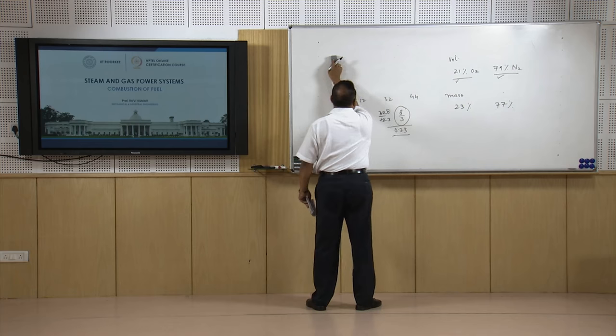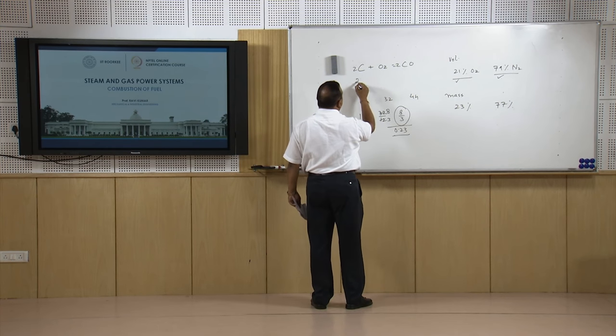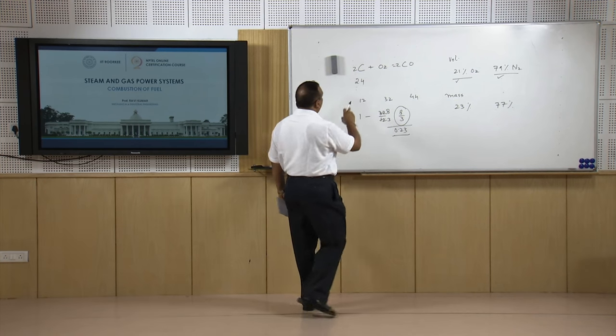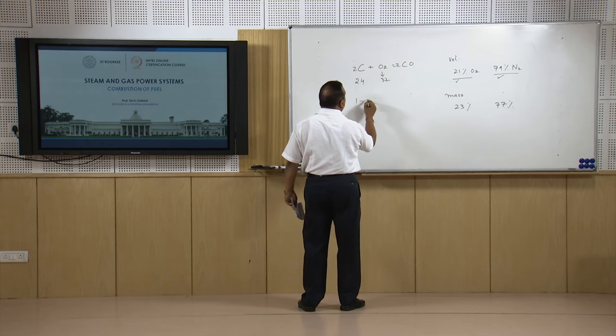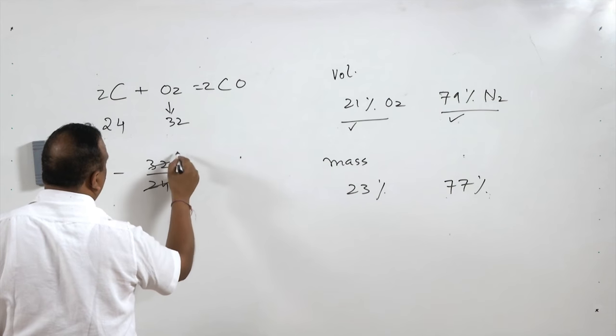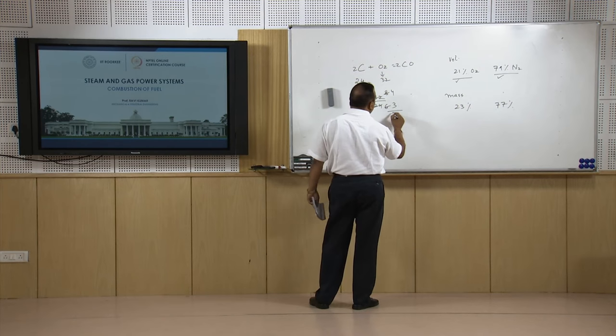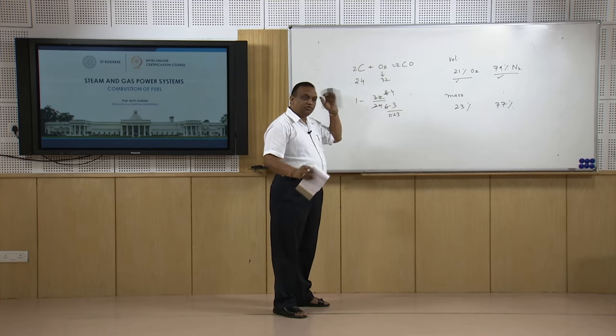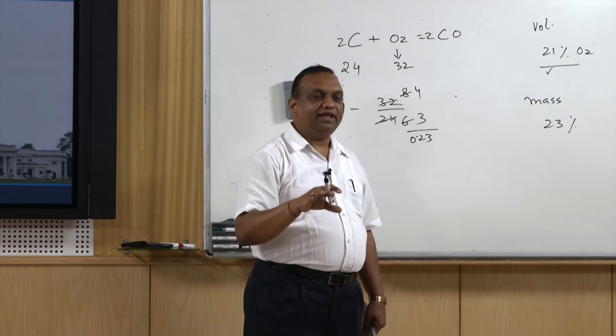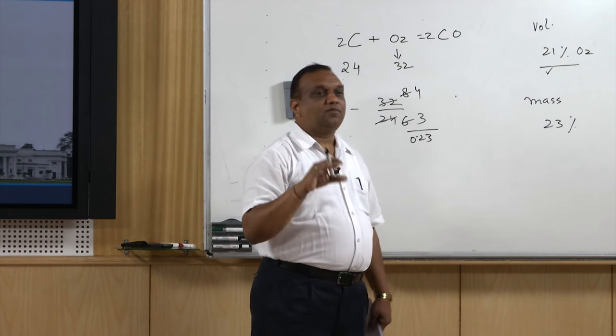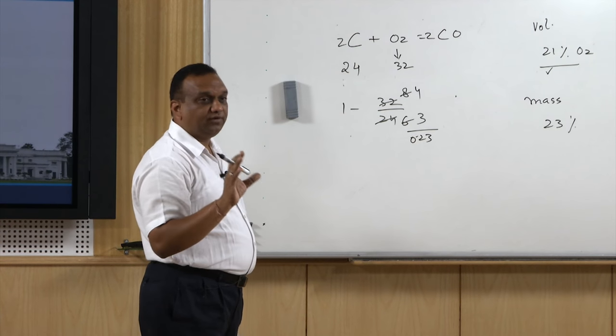For carbon monoxide formation: 2C + O2 = 2CO. Two moles means 24 kg of carbon requires 32 kg of oxygen, so 1 kg of carbon requires 32/24 kg of oxygen, divided by 0.23 to get the air. If both CO2 and CO are present in flue gases, we calculate the air required for each component and add them for the total air required.